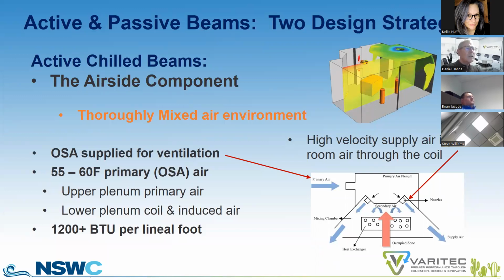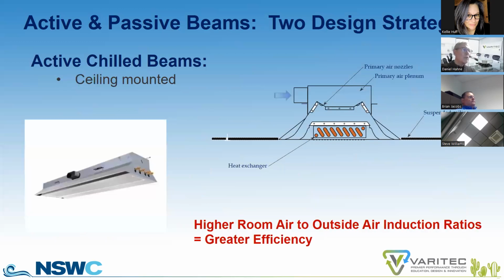A conventional active chill beam has air injected in the upper tier of a plenum, as discussed, and air is supplied at high velocity on opposite sides of a cooling coil. And by providing that primary air at 55 to 60 degrees, you can actually get 1,200 BTUs per lineal foot of capacity, more than you can in a passive chill beam device. So these are more cost-effective solutions. They may not be as efficient as a passive solution, but we're seeing regularly 30%, possibly more, system efficiency over and above medium pressure VAV.